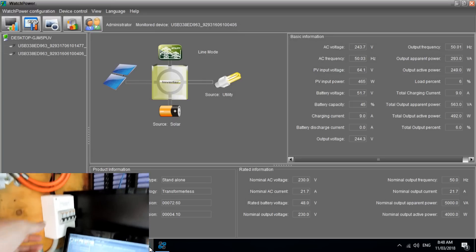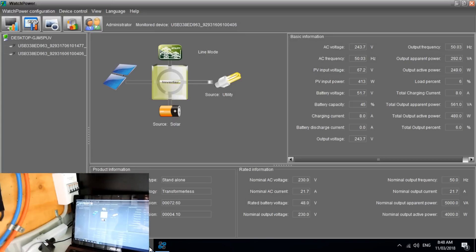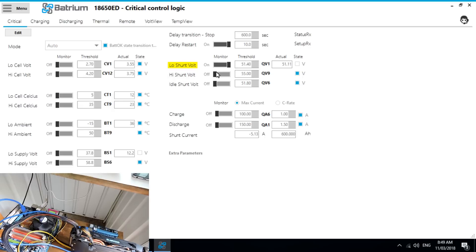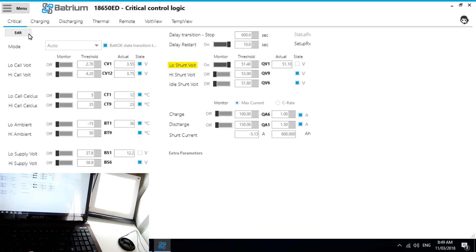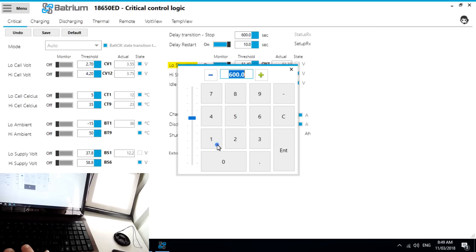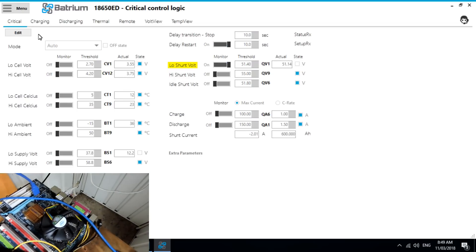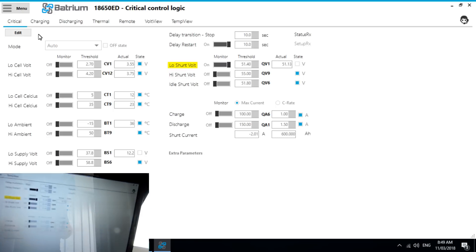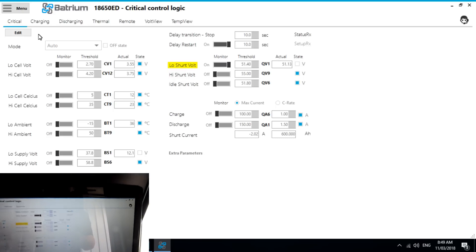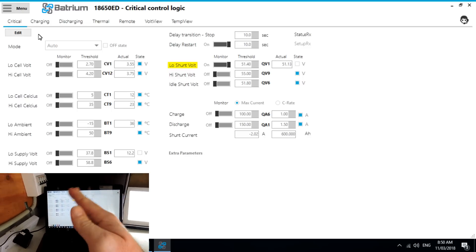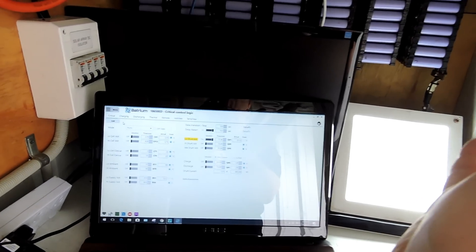I think I might speed this up a little bit by turning off my solar. There we go, that just clicked. We didn't change the transition delay stop, so we've got to change that to 10 seconds as well. Enter, save. That's actually turned off, so there we go it does work. You've got to do the transition stop and the transition restart to the time you want. Obviously I have it set to 600 seconds which is 10 minutes, so it's got to completely go past it before it'll change states. This is because you might have a load at that point in time where you get a lot of sun or you might have the dryer on, so you don't want it clicking backwards and forwards because these relays do have a limited lifespan.